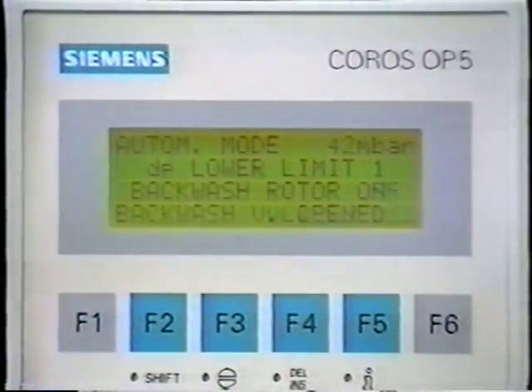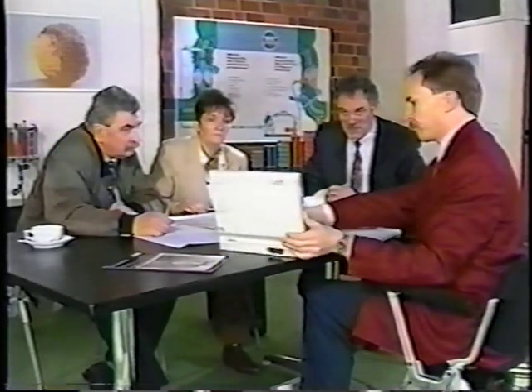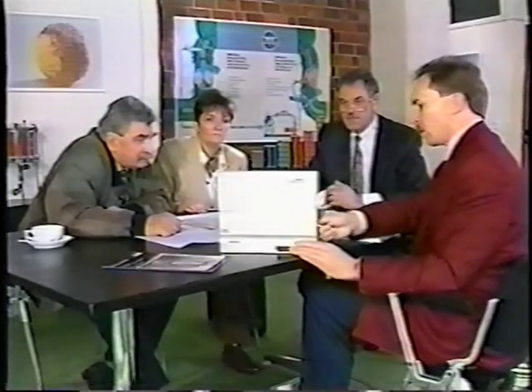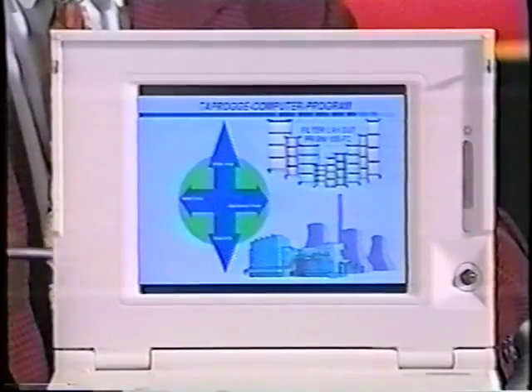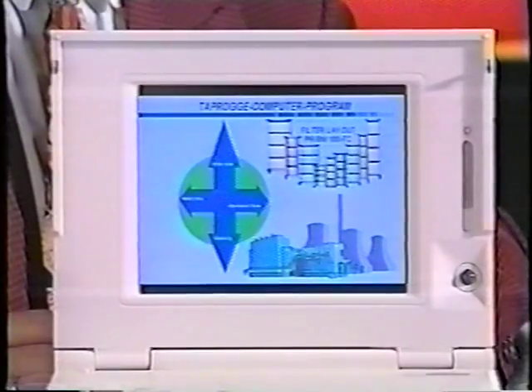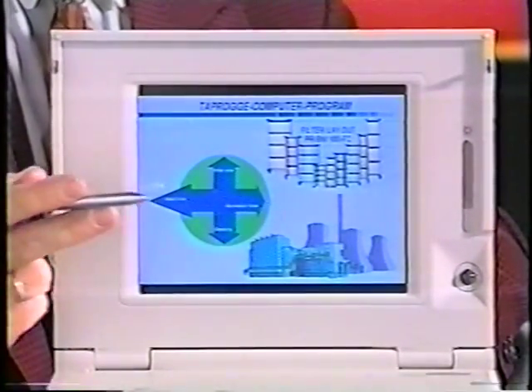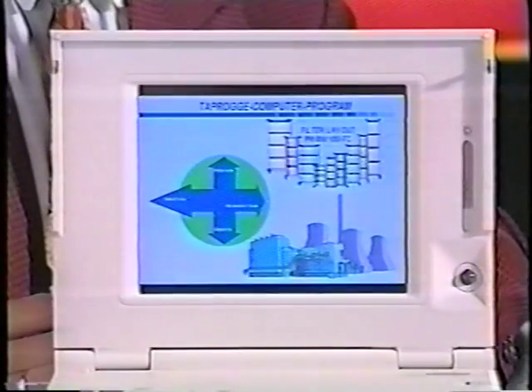The backwash process is stopped when the differential pressure across the filter elements reduces to the value set for a clean filter. Fine filters from Taprogge are designed for each specific application. The results of extensive laboratory testing of a wide range of filters form the basis of a computer-aided expert system. By collating the four main filter design factors, size of construction, pressure loss, backwash volume, and debris capacity, it's possible to design the optimum filter for each application.